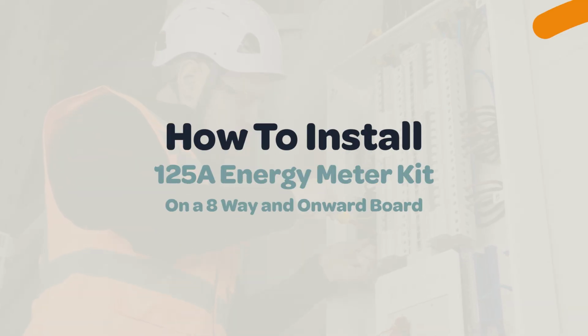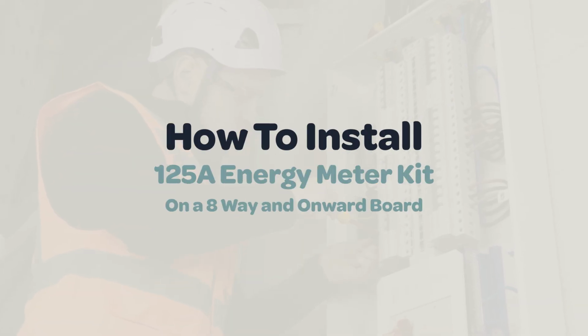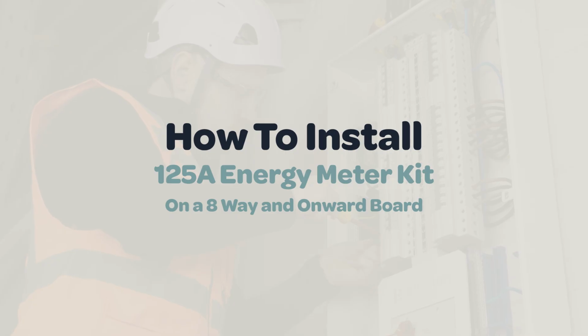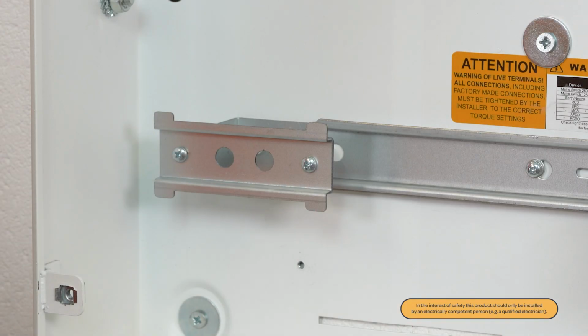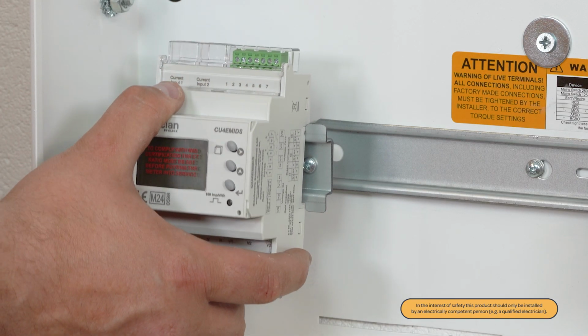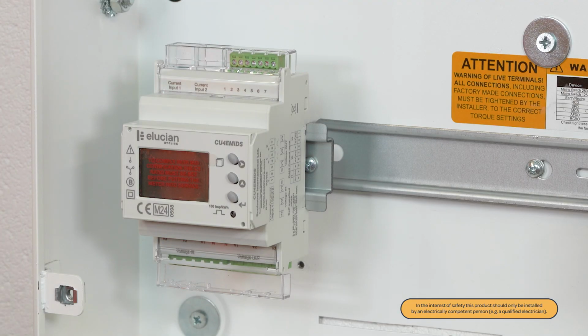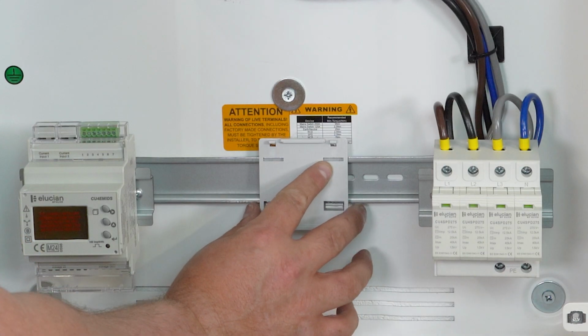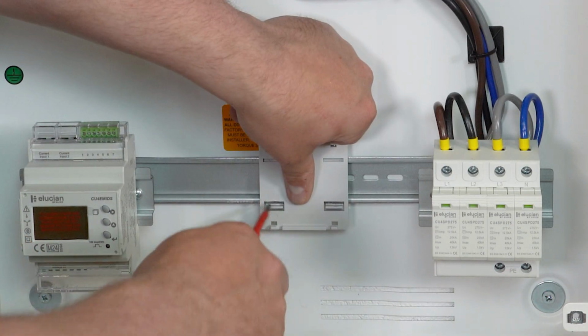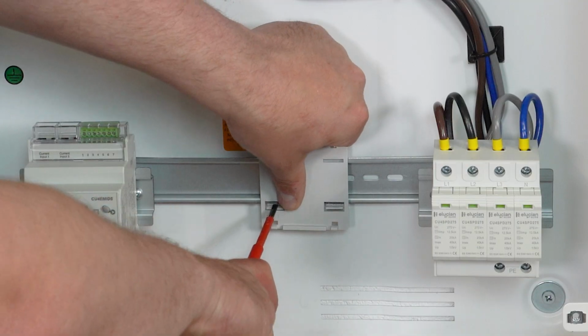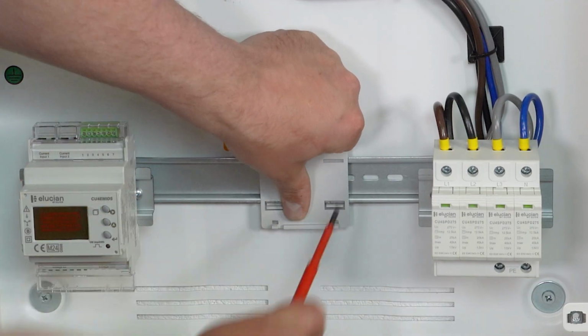How to install a 125 amp energy meter kit on an 8-way and onward board. Start by securely clipping the energy meter onto the rail for correct placements. Attach the current transformer mounting bracket onto the DIN rail. A screwdriver can be used to move the tabs to attach it into position.